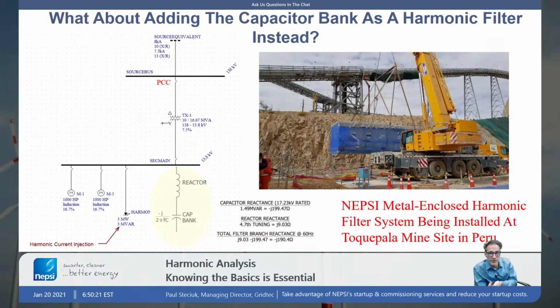much lower than the value of X of C. For a typical fifth harmonic filter, the value of X of L is 1 over the tuning point squared. So calculate your value of X of C, divide by 25. That's your fifth harmonic impedance of that reactor. So the reactor is 1/25 of the capacitor, which means that a harmonic filter bank puts out reactive power at the fundamental.